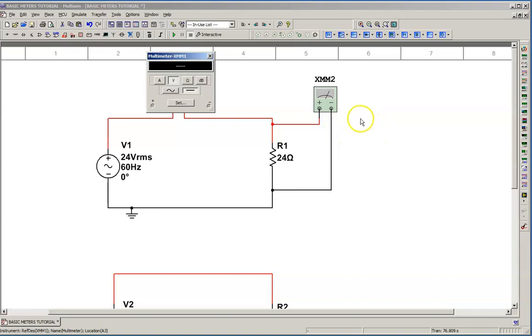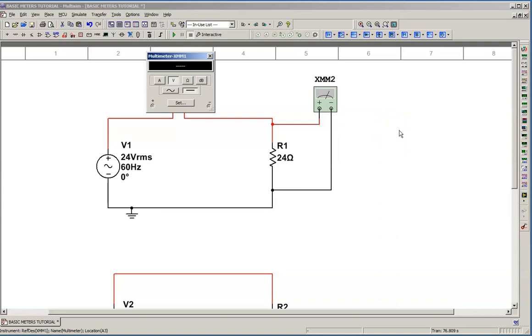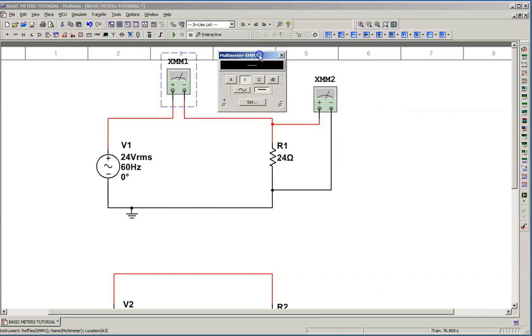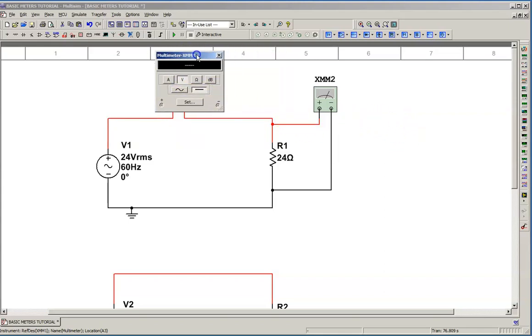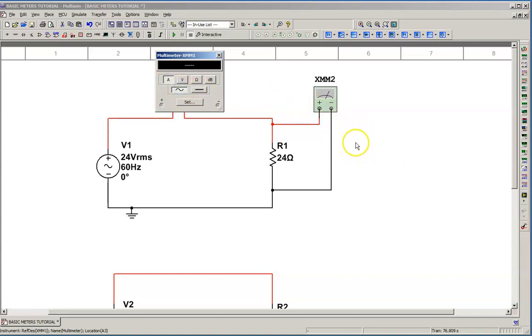If you do have a multimeter and it has a current function where you can measure current, make sure that you do not select that function with your leads in those current jacks because you could possibly short out the circuit and damage the meter and cause an even worse scenario to happen. So, notice I clicked on the meter and I have my controls up and it's set for volts DC. So, that's the default setting. We want to measure amps, AC. So, keep that in mind, please.